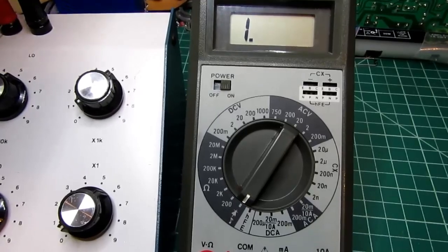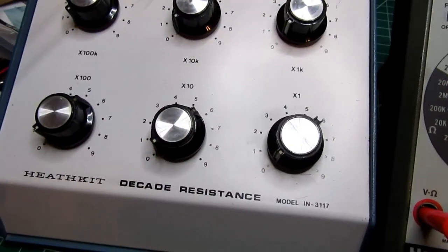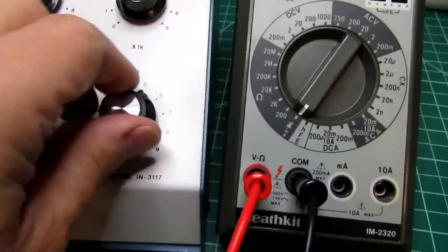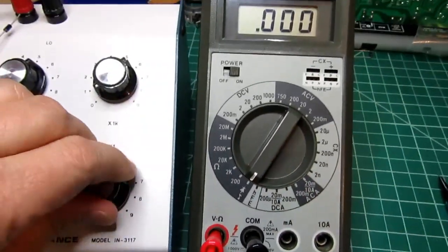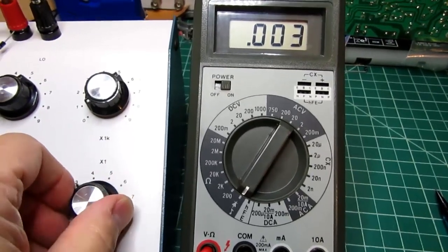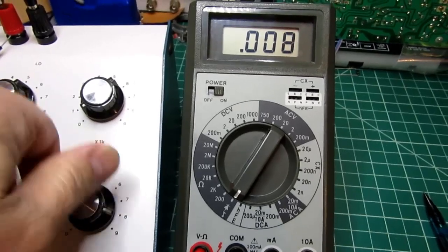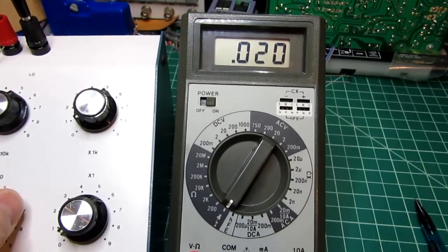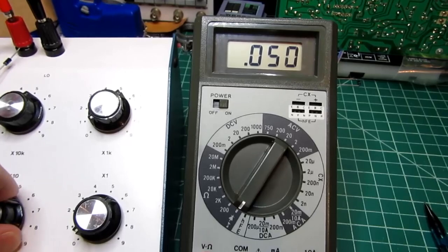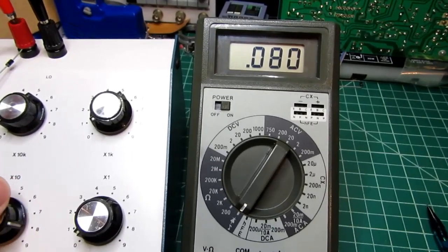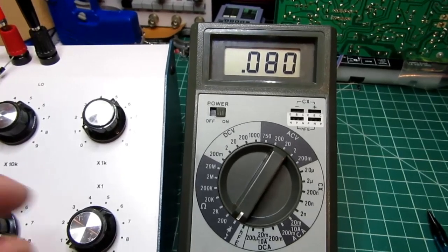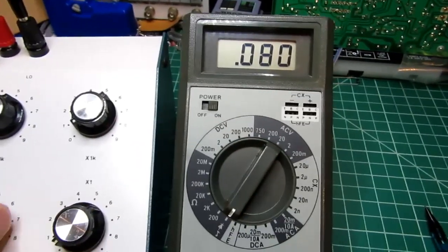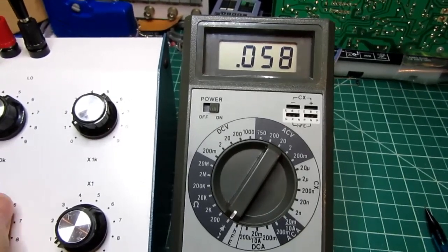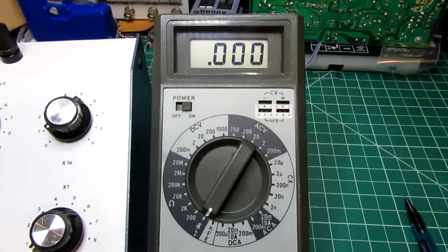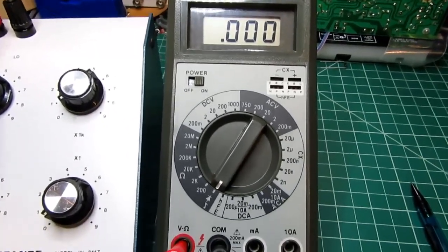Now if I connect this up to my resistance decade box, let's start cranking up the resistance. That's 1 ohm. Up to 9 ohms, it doesn't see any difference. Let's go to 10 ohms, 20, 30, 40, 50, 60, 70, 80. At 80 ohms it stops saying continuity, although it keeps reading the resistance value. So continuity according to this meter is anything below approximately 80 ohms.